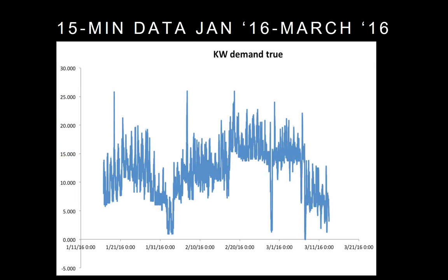But even in this chart, you can see the maximum kW on a day in a given month would be over 25 or 26 kW. Many of the commercial systems we were looking at that did peak shaving started at 24 kW of power, so they were out of our price range for sure. We were really operating on some assumptions and had to go with those. We didn't have a good measure of exactly what the demand was that we needed, but we definitely started looking at that data.